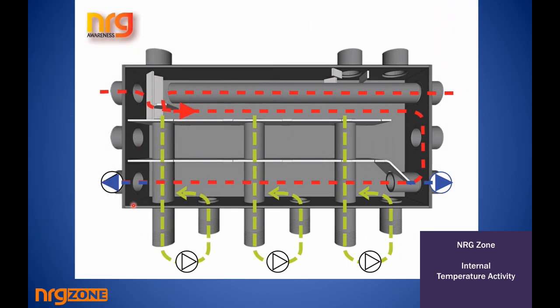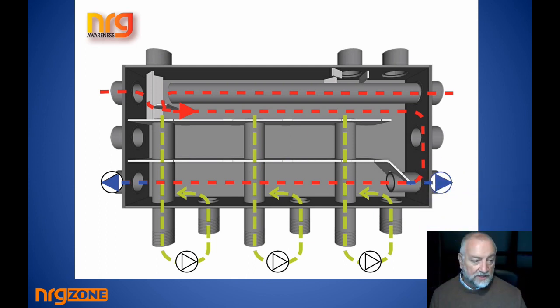Now you can see just close up here, we have the flow coming in, we have the returns going back to our boilers on the left or right, or cross flow if we wish, and then you can see heat being drawn from the top chamber through a respective pump with respective pipe sizing, so that you can set your flow rates for the first zone to be different to the second zone and third zone or whatever. Each one of them has equal access to the hottest water. Each one can deliver back to wherever you want it to go. This is just an example of one of those configurations.